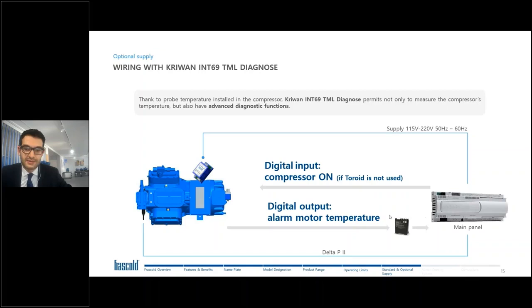This is the first option: to add, in addition to the components that you have already seen, a diagnose module that gives you more information about errors, about the number of switching on and off, about how many times the compressor remains on, and so on. It gives you diagnostic features and a lot of information about how the compressor is working, if it's very near to the threshold or far from the threshold. So you can understand if the compressor is working properly or not.